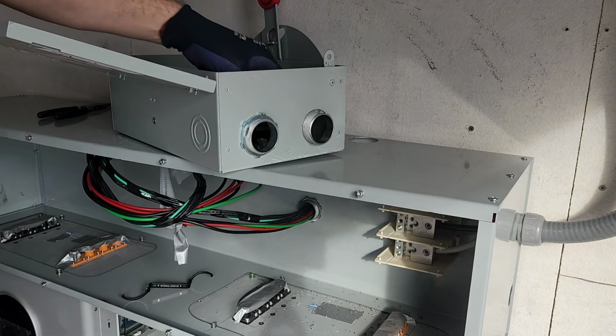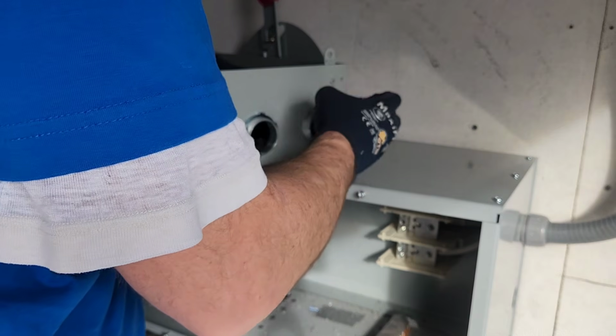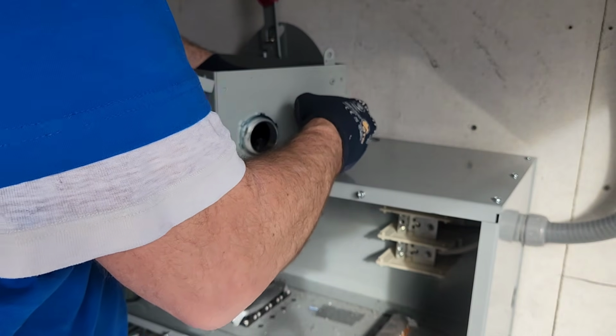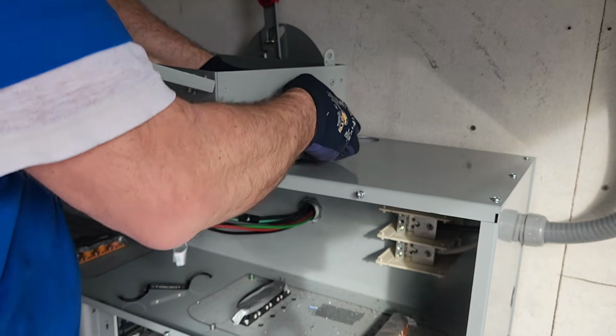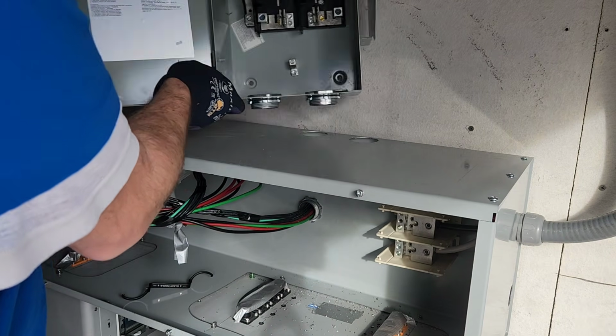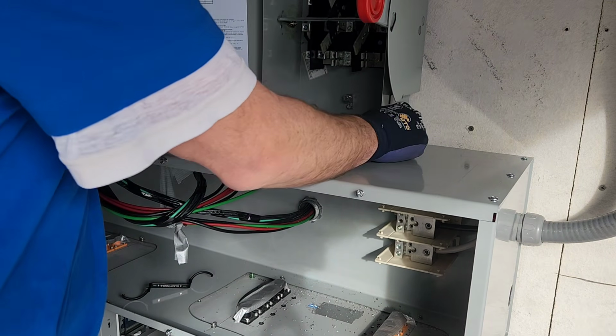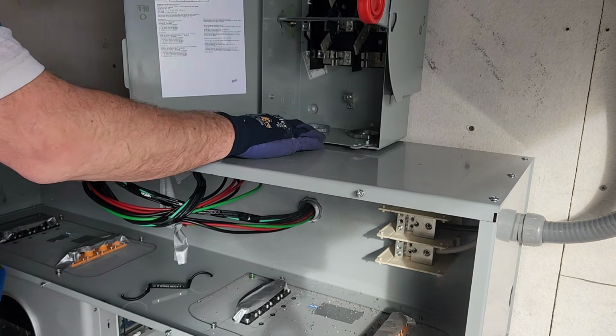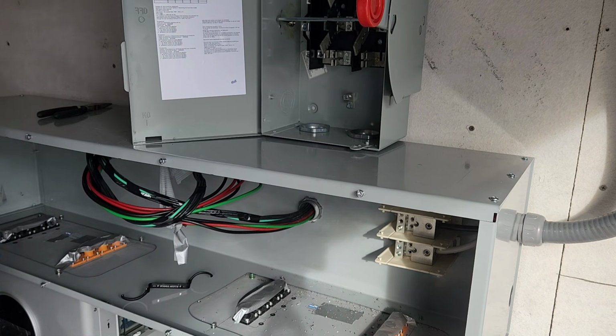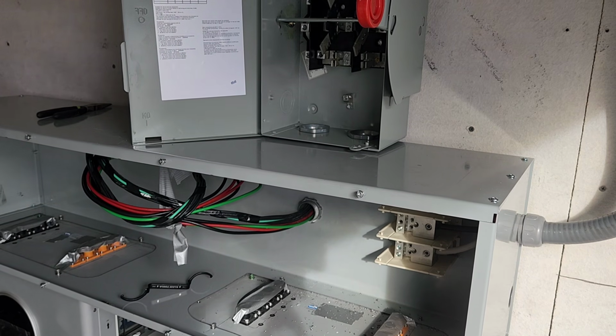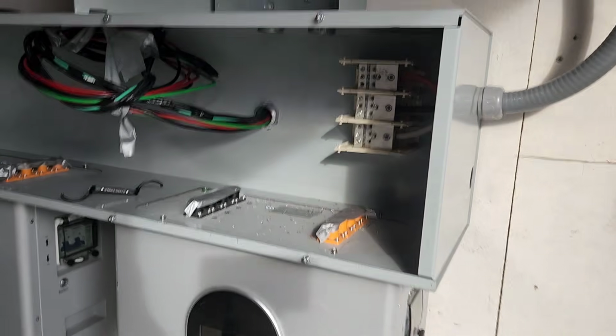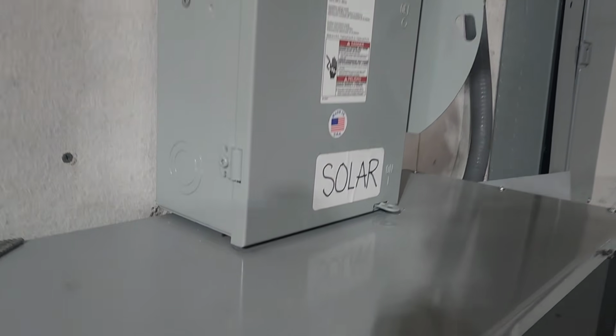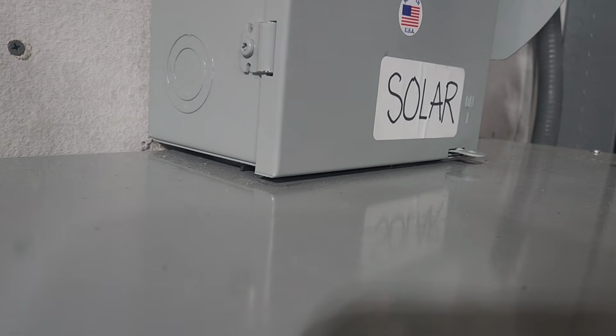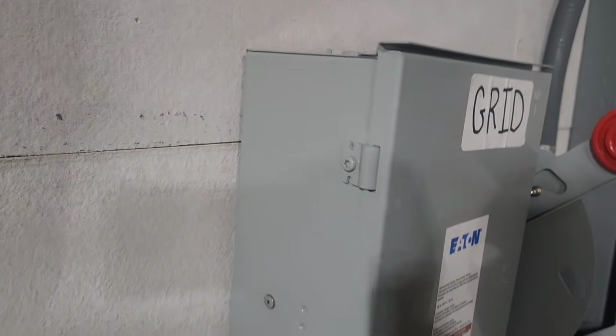So here I am using chase nipples and also a rigid lock nut. I use the chase nipple to make sure I don't have any sharp edges for the wire to rub on. They also have insulated chase nipples, which would probably be better, but this nipple is fairly smooth. I'm putting a lock nut between this transfer switch and my wire gutter just to leave an extra gap so the door to the transfer switch can open a little easier.